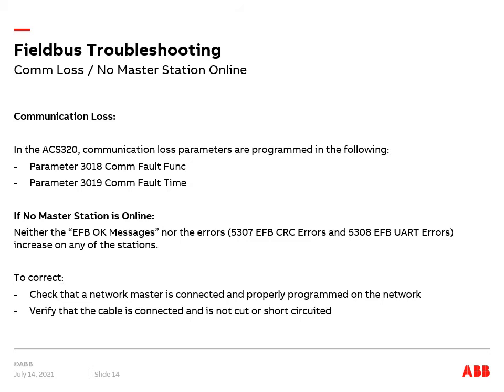What if no master station is online? Neither the EFB OK messages nor the errors found in 5307 EFB CRC errors and 5308 EFB UART errors increase on any of the stations. To correct this problem, check that a network master is connected and properly programmed on the network, and verify that the cable is connected and is not cut or short circuited.